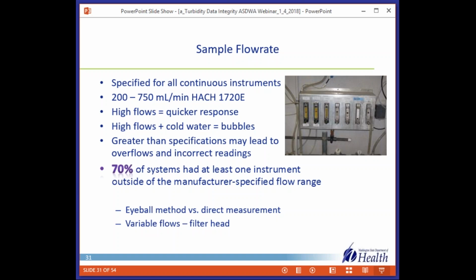There are sometimes issues with variable flows coming from changes in filter head. This could be fixed by putting in a constant head tube on the front end of your turbidimeter. The main takeaway is you have to measure and document on a routine basis. Lots of questions about, well, what is the best number? We think that 500 mils per minute appears to be a good starting point. A flow may need to be reduced if you have air bubbles, or if there's a problem with water conservation at the treatment plant in question.